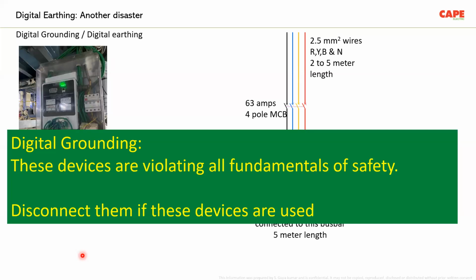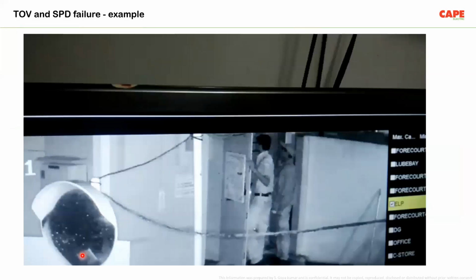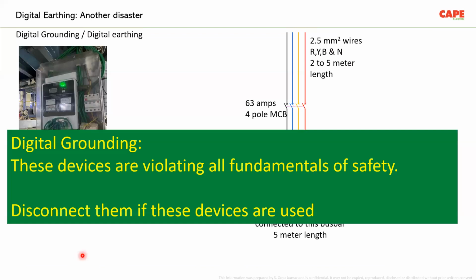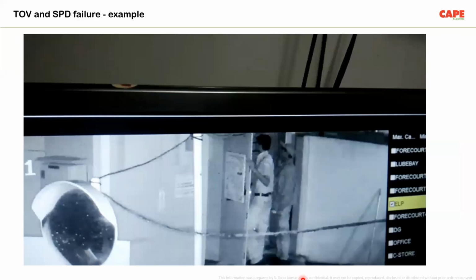Now, if you have functional earth, which we also call isolated earth, for the electronic equipment, the way of handling is different. So you have to have a functional earthing system. It has nothing to do with the safety earthing system. So the simple recommendation is, if you use a digital grounding device, please disconnect it immediately. Of course, I know that you must have spent a lot of money on these particular devices. Of course, the easiest way is, please disconnect it. Otherwise, you will be in much deeper problem.